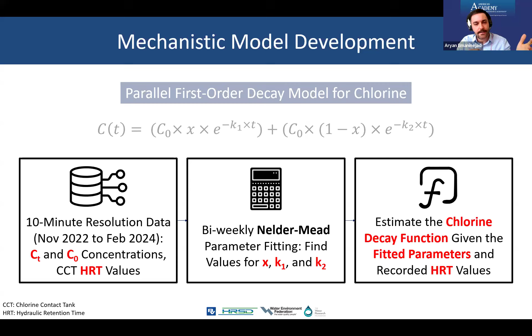We ran this parameter fitting approach every day using the previous 2 weeks of data. So every new day we have a new model that tells us the chlorine decay considerations in our chlorination process using the previous 2 weeks of data. The reason is to make sure we have an updated model. Using that, we can estimate the chlorine decay function given the fitted parameters and the recorded HRT values at the plant.